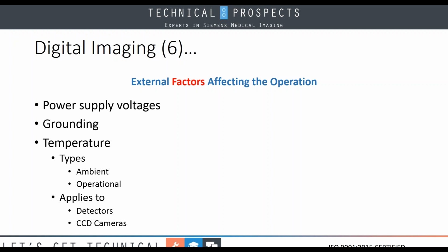This is going to look at detectors and CCD cameras. Now, let me explain something about the CCD cameras. In one of my former lives, we actually had one that operated at minus 23 degrees centigrade. Putting this camera on, there was a 10-minute wait period before the operators were allowed to do anything. And that helped us ensure that we would get good quality images. Hence this temperature factor that we talk about. With detectors, we have operating ranges that they have to be in. We need to ensure that they're there.